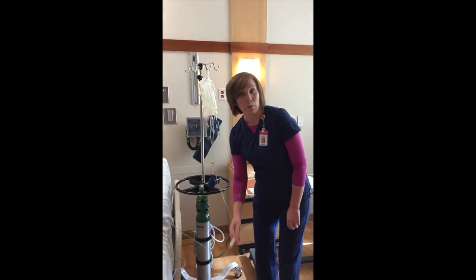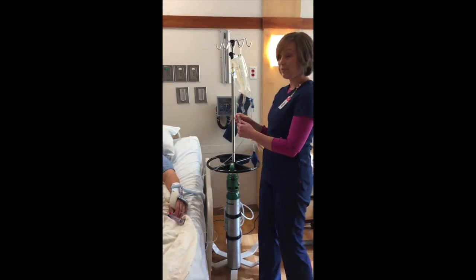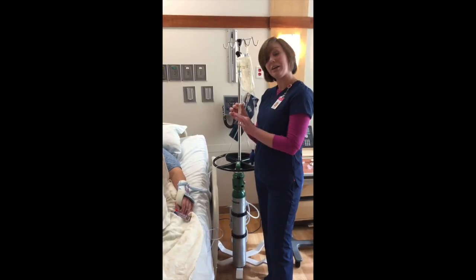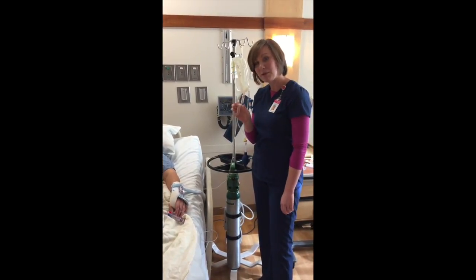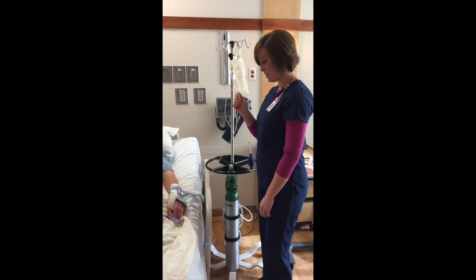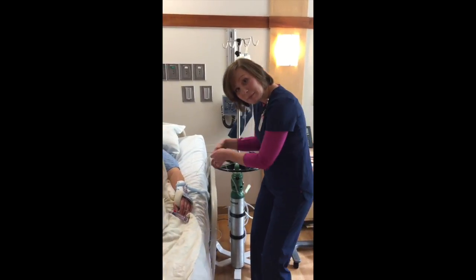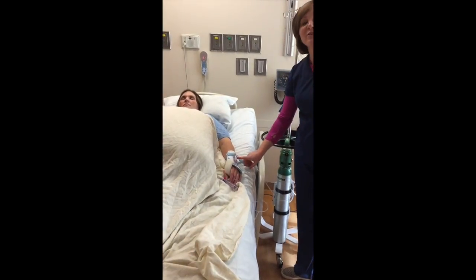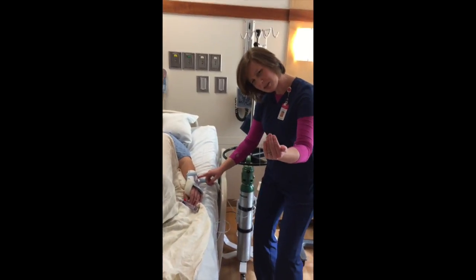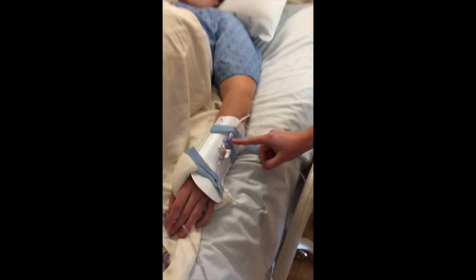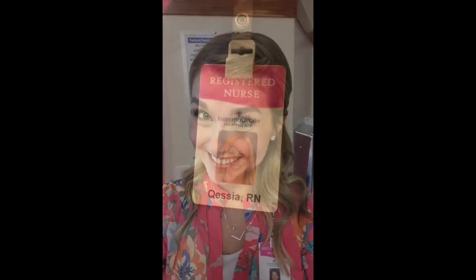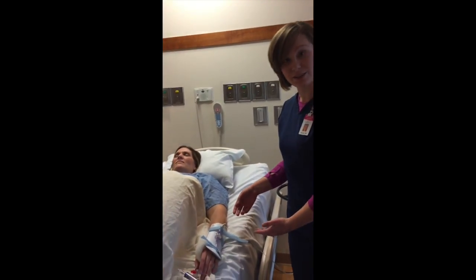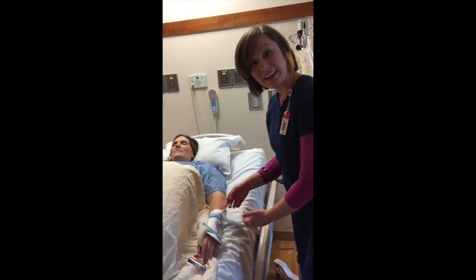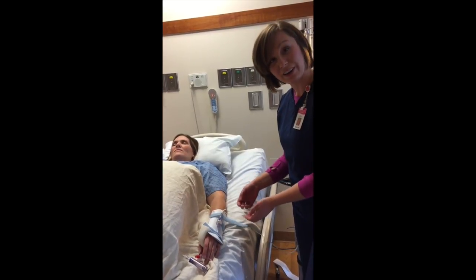Then as we follow our way down this line, you've got a roller clamp here. When in use, your roller clamp should never be closed, so you always want to check that as well. As we go a little bit further, you have your transducer right here. Come in close, come check this one out. Want to know how I know that's a transducer? Because of the way it is. So as we were talking about the transducer, it is what reads our patient's blood pressure.